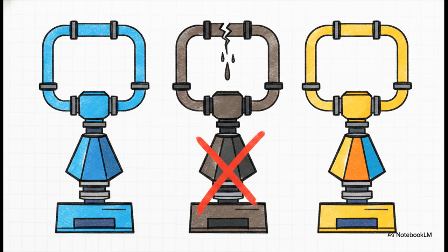This is a very strict, deliberate redundancy choice by the naval architects. If one cooling loop fails, clogs, or springs a leak, it should only ever take down that single corresponding thruster. By keeping the water loops physically isolated from one another, a minor fault in one subsystem can never wipe out multiple thrusters and compromise the whole ship's ability to hold its position over the well.